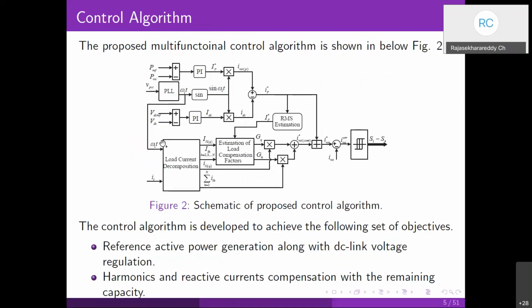We are getting this theta of the fundamental voltage component from the PLL. You can see here we can sense these load currents, and these load currents are being decomposed into harmonic, reactive and active components. Based on these harmonic and reactive components, we estimate their RMS values, and then we estimate the compensation factors for the voltage source inverter. Basically the main purpose of this control block diagram is to derive the reference current signals for the voltage source inverter.